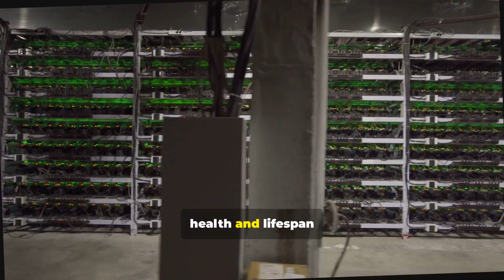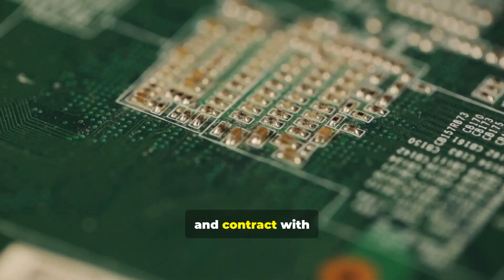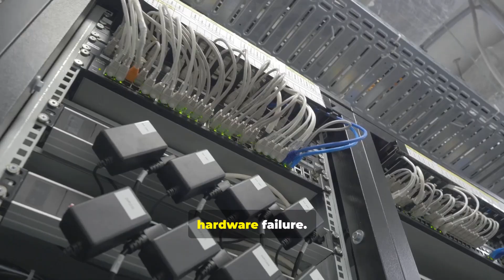The operational advantages of the granite environment extend down to the health and lifespan of the individual pieces of IT equipment. The highly stable thermal conditions reduce thermal stress on electronic components. Materials expand and contract with changes in temperature. Over thousands of cycles, this can cause solder joint fatigue. It can create microfractures on circuit boards, and ultimately lead to premature hardware failure. By maintaining a near constant temperature within the data hall, the underground environment minimizes this wear and tear. That contributes to a longer, more reliable operational life for servers, for network switches, and for storage arrays.